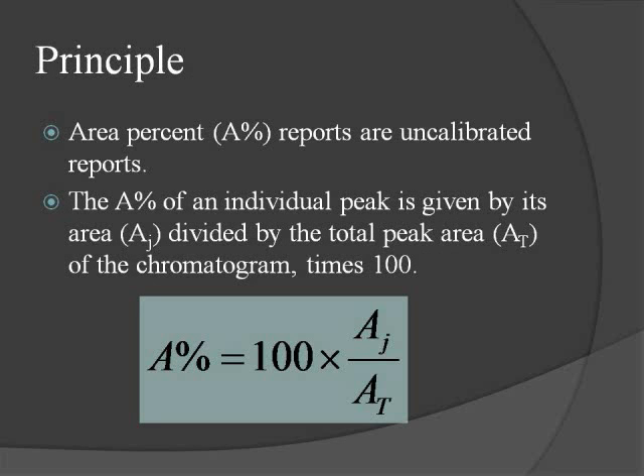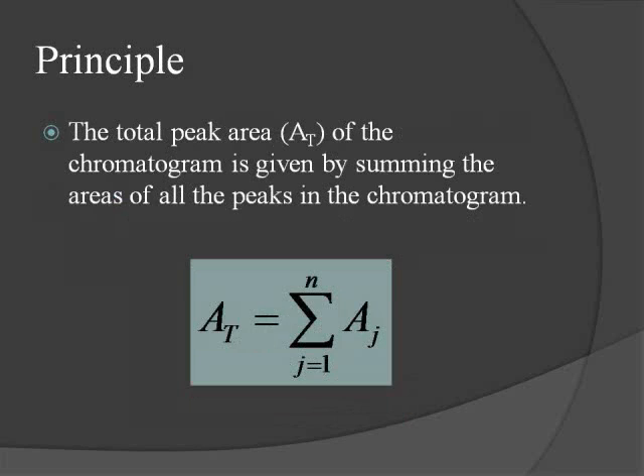As we said earlier, area percent reports are uncalibrated. The area percent of an individual peak is given by its area divided by the total peak area in the chromatogram, the quotient multiplied by a hundred, as you see in the equation. The total peak area of the chromatogram is given by summing up all of the areas of all of the peaks in the chromatogram. It's at this point that one of our assumptions can get in our way. If there is a peak in the sample which does not respond to the detector in use, it will not be accounted for in this procedure.